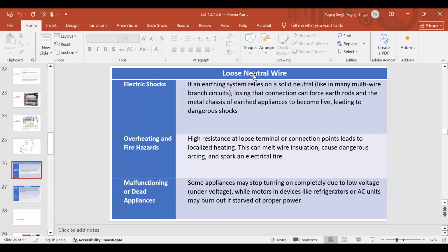So that loose neutral wire is very, very important to be checked. If my neutral wire is loose, I may get electric shocks. If an earthing system relies on a solid neutral, like in many multi-wire branch circuits, losing that connection can force earth rods and the metal chassis of earth appliances to become live, leading to dangerous shocks. So if earthing is not proper, that body of the gadget can become live. Otherwise, even if some leakage is there, earthing system is working properly. So it will take the dangerous voltages away from the body.